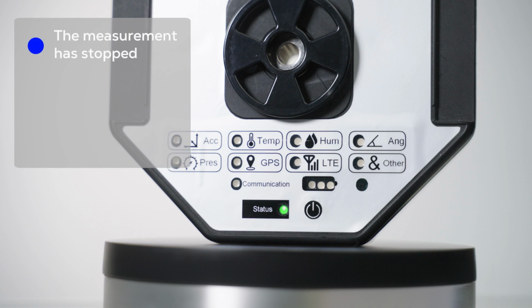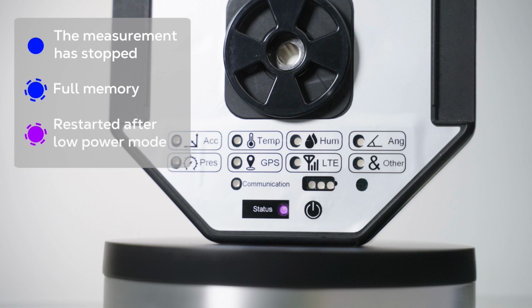If the LED shows blue, the measurement has stopped because it reached its scheduled end date. The device is no longer active. A blinking blue LED means the measurement stopped because the memory is full. A blinking violet LED shows the device has restarted after being in low power mode, which can happen if the button was pressed or the battery was changed. Press the button again to view the normal status of the device.